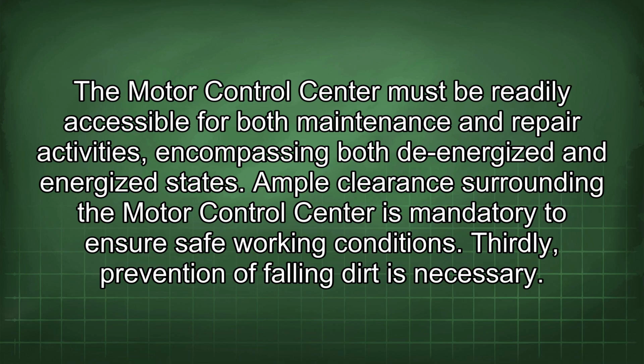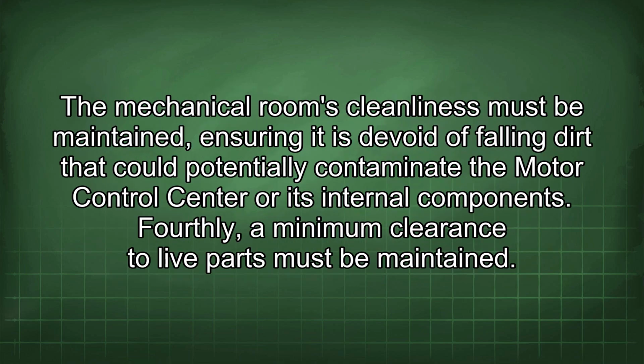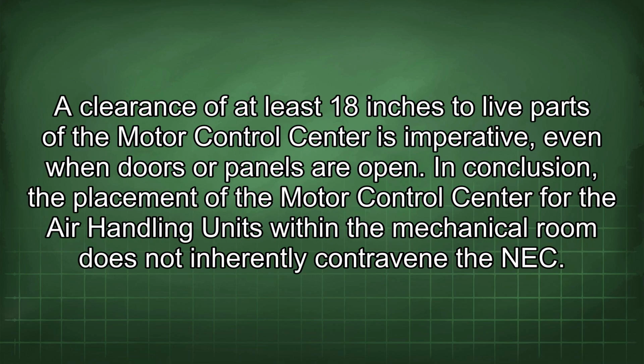Thirdly, prevention of falling dirt is necessary. The mechanical room's cleanliness must be maintained, ensuring it is devoid of falling dirt that could potentially contaminate the motor control center or its internal components. Fourthly, a minimum clearance to live parts must be maintained. A clearance of at least 18 inches to live parts of the motor control center is imperative, even when doors or panels are open.